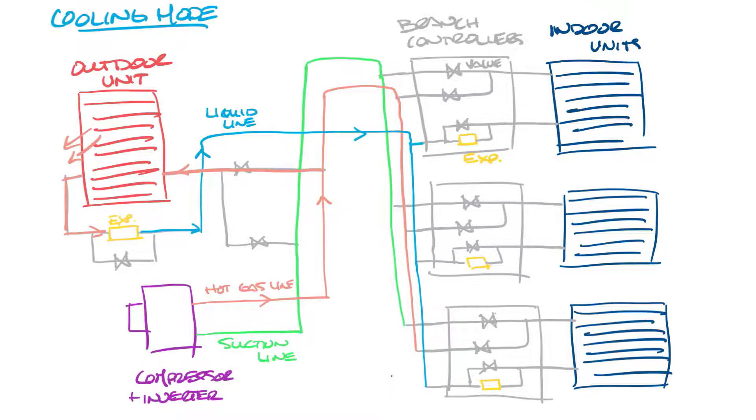And now it'll flow through the liquid line to each of the units. It doesn't need to go through the expansion device here because it is already cool and it's sent into the indoor units which sends cold air into the space and cools the space. From there the refrigerant flows out into the suction line and back into the compressor. And then it starts that process again. So any valve in our drawing that doesn't show flow going through it is closed.